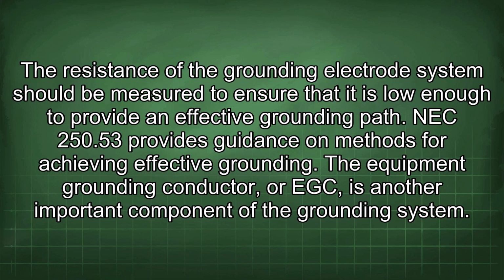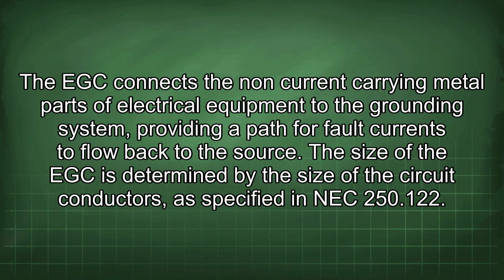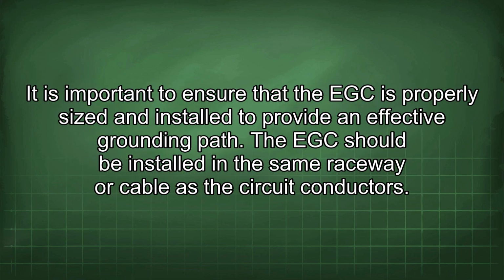The equipment grounding conductor, or EGC, is another important component of the grounding system. The EGC connects the non-current carrying metal parts of electrical equipment to the grounding system, providing a path for fault currents to flow back to the source. The size of the EGC is determined by the size of the circuit conductors, as specified in NEC 250.122. It is important to ensure that the EGC is properly sized and installed to provide an effective grounding path. The EGC should be installed in the same raceway or cable as the circuit conductors.